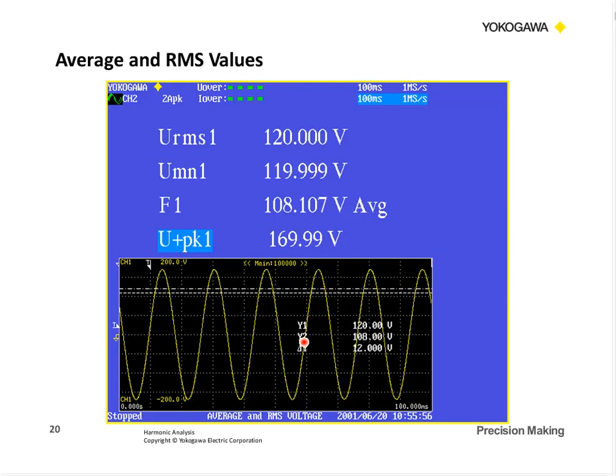Here's a display of one of our power analyzers. We hooked it up on a calibrator, and we had 120 volts RMS. This is what we call the mean value, that half cycle average, the mean value, scaled to RMS. So this does the half cycle mean average with the 1.11 multiplier, and basically it's 120 volts. And so our average, we went in and did the actual half cycle average or mean measurement at 108, and if you multiply that by 1.11, that should come out to 120. And then, of course, our peak on the sine wave should be square root of 2 times that. So graphically, that's what we have.